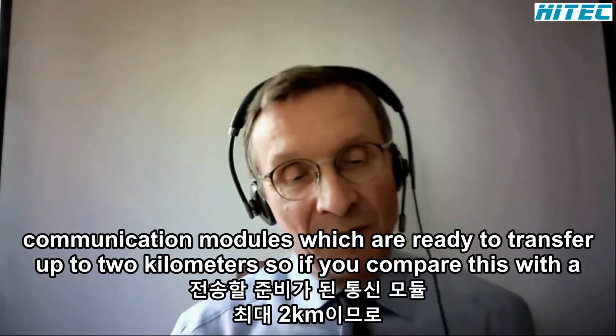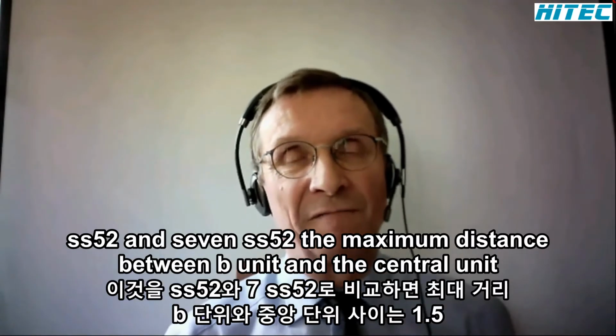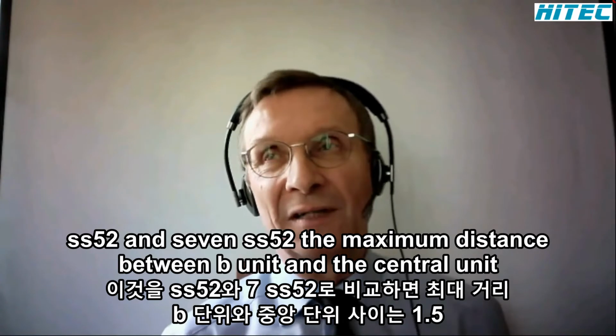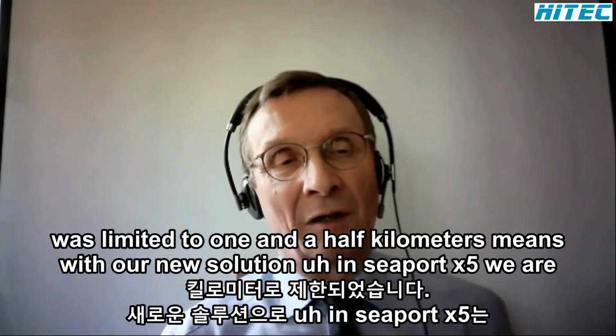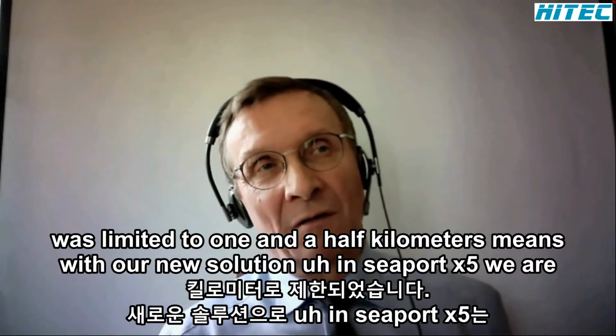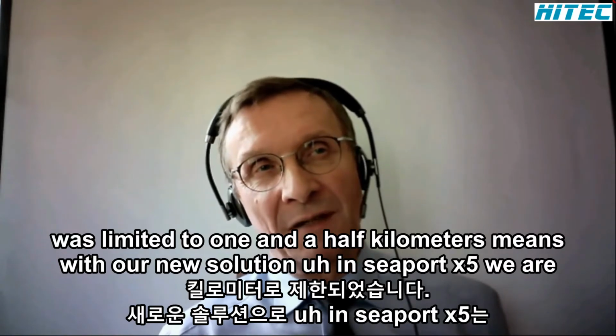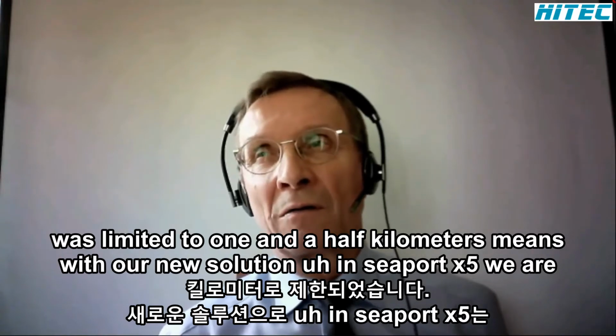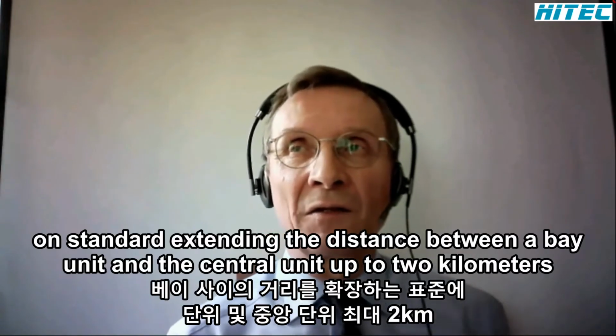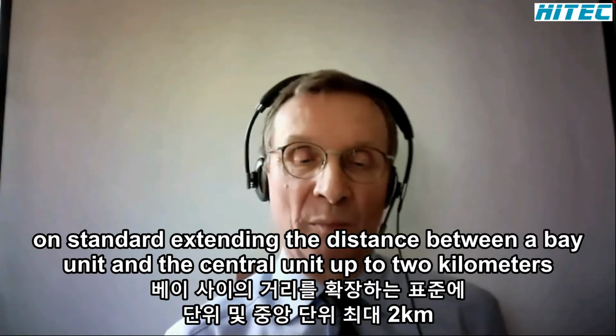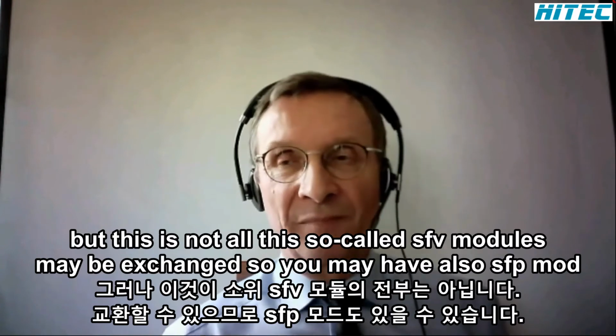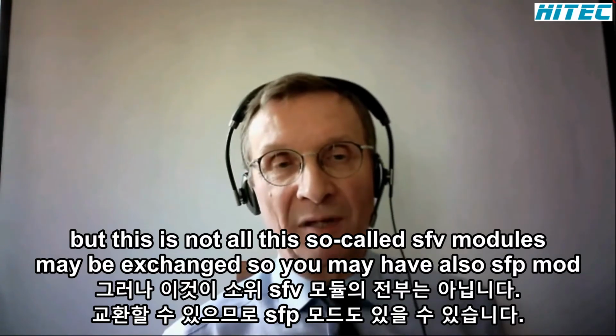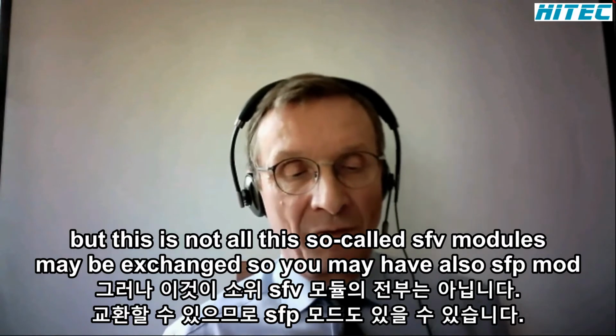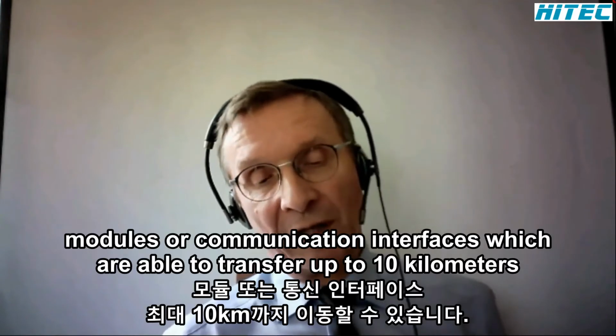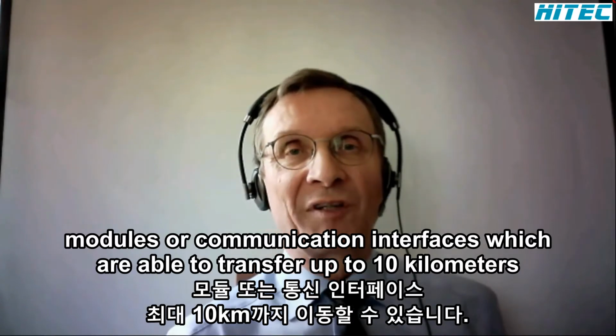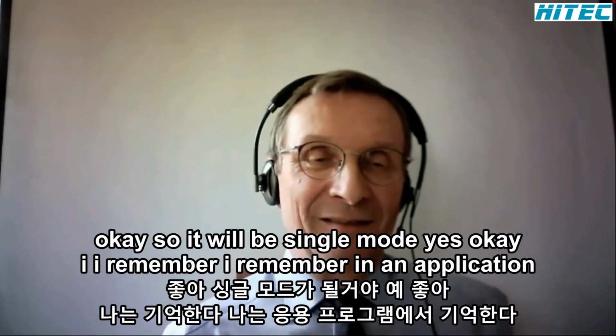If you compare this with the 7SS52, the maximum distance between bay unit and central unit was limited to 1.5 kilometers. This means with our new solution in SIPROTEC 5, we are by standard extending the distance between a bay unit and the central unit up to 2 kilometers. But this is not all. These so-called SFP modules may be exchanged. So you may also have SFP modules or communication interfaces which are able to transfer up to 10 kilometers. Okay, so it will be single mode.